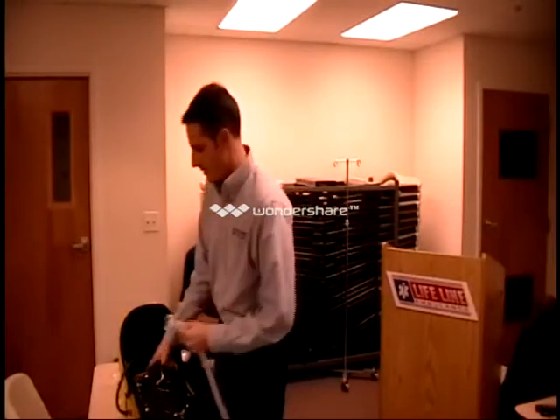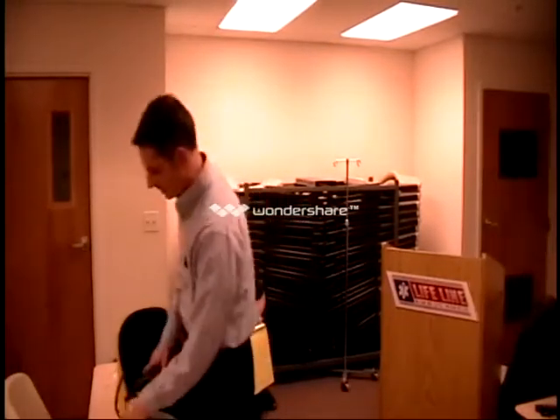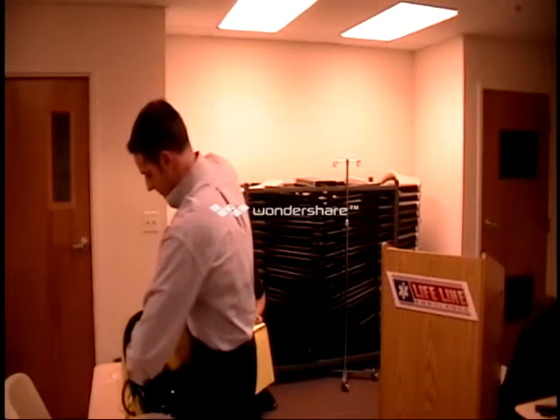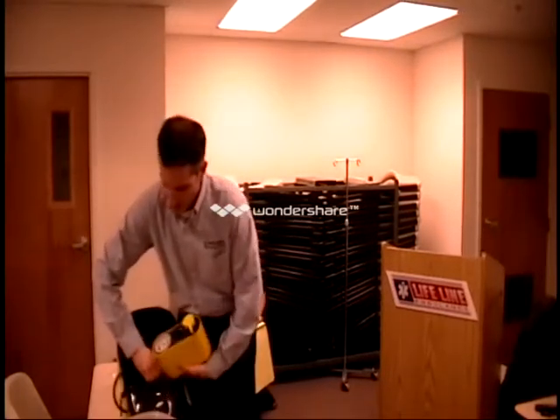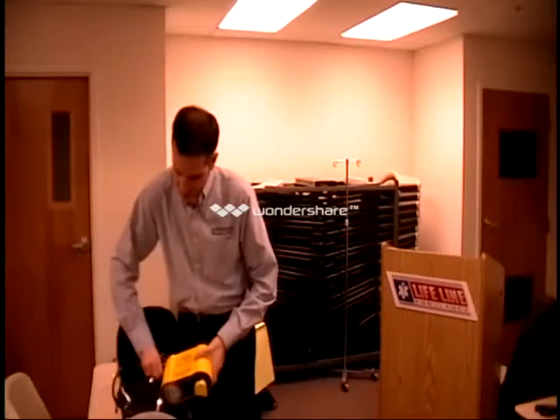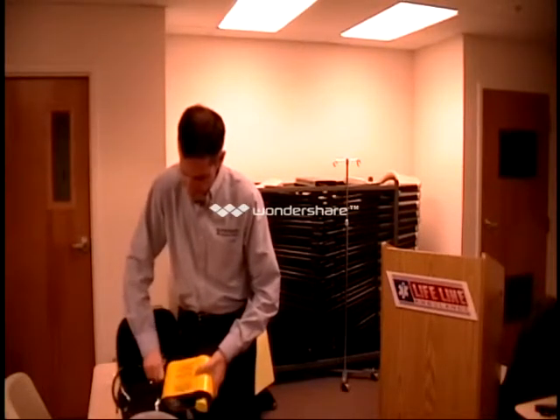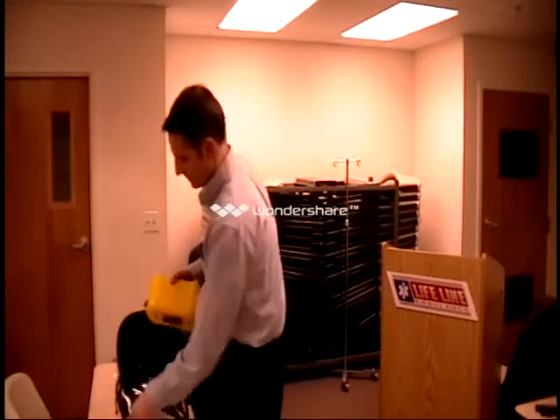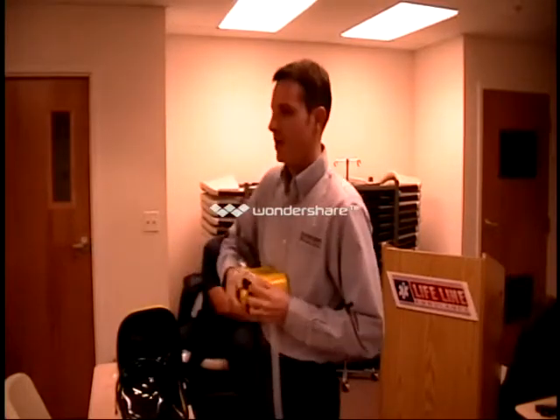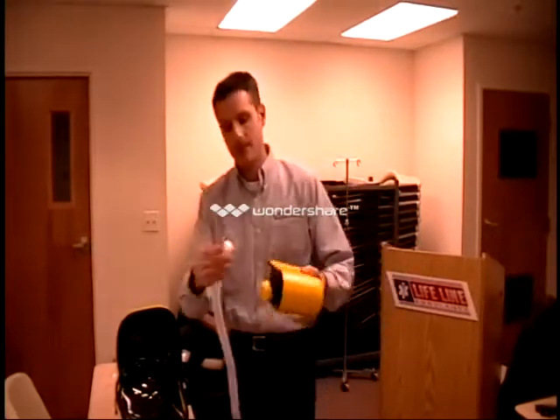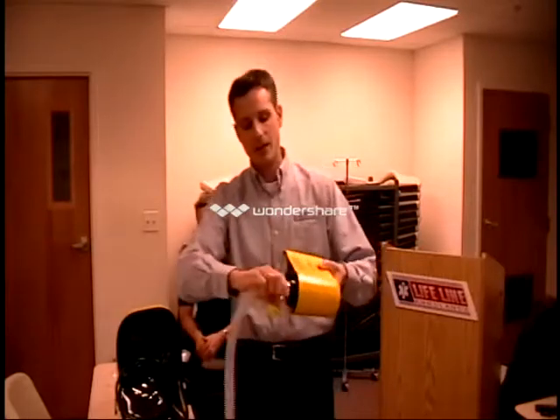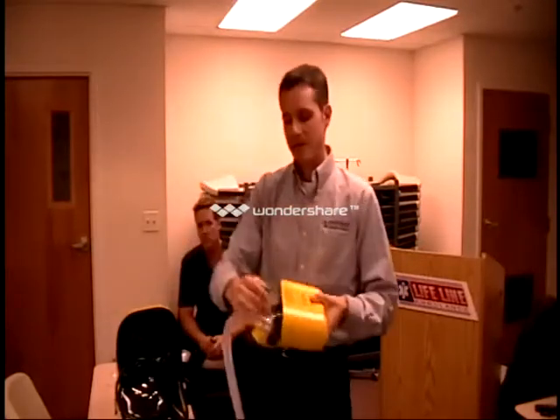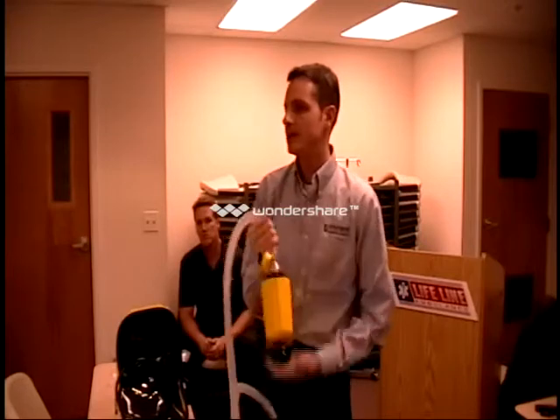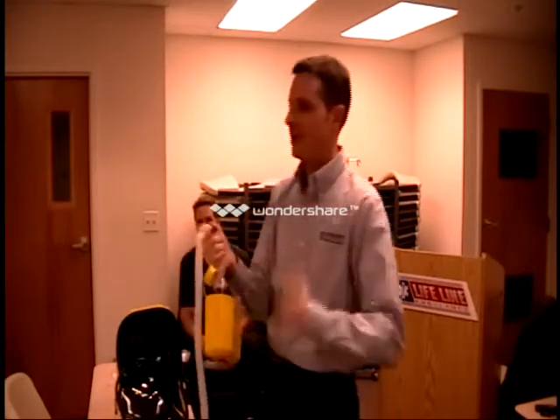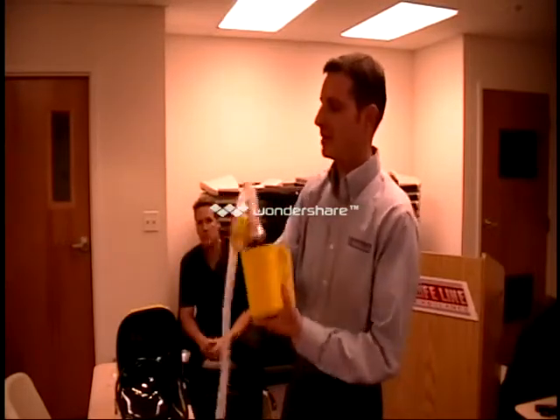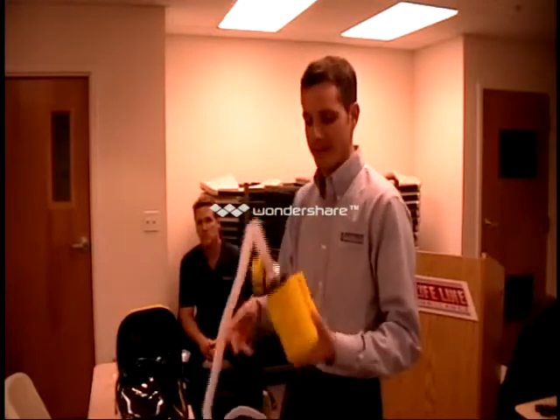This attaches to the unit. The outlet port has 2 little tabs on that breathing circuit. The way you attach this, there's 2 tabs here. Just push straight in, and clockwise turn until both tabs lock up underneath the flanges here. Stays locked into place. You don't want this coming disconnected when you've built up airway pressure on the patient. So make sure it doesn't get disconnected coming around a corner, doorknob, or anything.